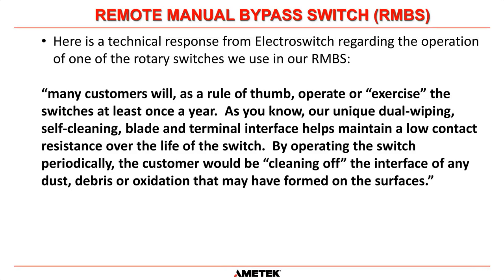So every time you move the switch from one position to another, there is a self-cleaning blade and terminal interface, and the mechanism wipes the surface to maintain a low contact resistance. So operating the switch really does help keep those contacts in a clean mode of operation and prevents high resistance connections there. So it is important that you operate your remote manual bypass switch on at least an annual basis. And that's part of the maintenance that AMETEK Field Service supply.